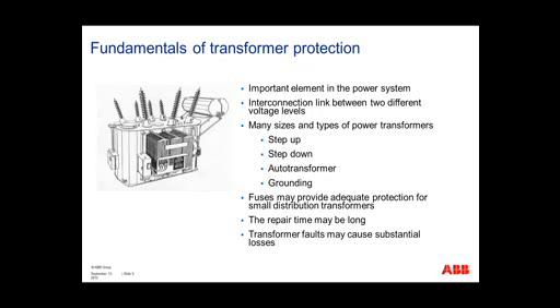So what is the transformer? The transformer is one of the most important parts of the power system. The reason for this is it is your interconnecting link between two voltage systems. The reason you need a transformer in your system, of course, is either to step up or step down the voltage and the current coming out of typically a generating plant. If you just tried to transmit the power coming out of this generating plant, you would see a lot of losses in the transmission system based on your I²R losses.